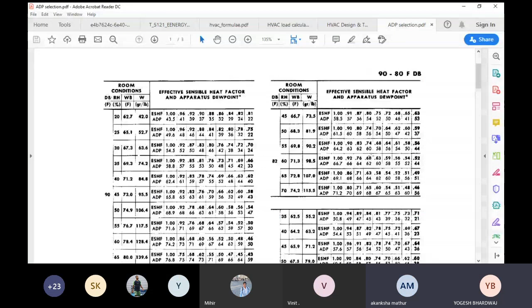Like you calculate ADP directly from the psychrometric chart, or we can calculate the ADP from this chart as well. So if I'm taking my design condition as 75 degree Fahrenheit and 55 RH. This column is showing RH. So in this table and this particular row, this area, this is my 75 dry bulb, 55 RH. This is my inside room condition that I am considering for my heat load calculation.